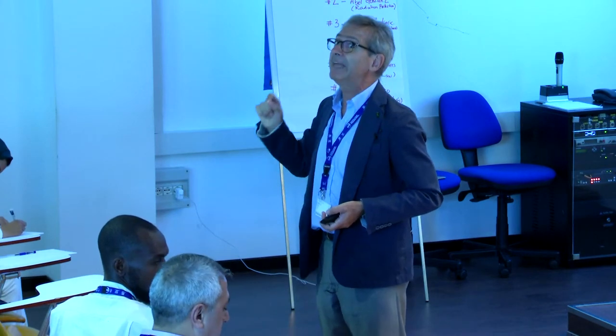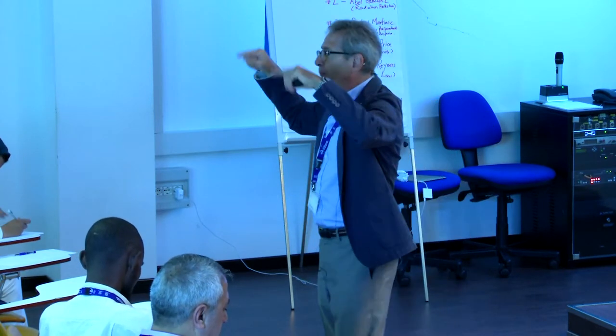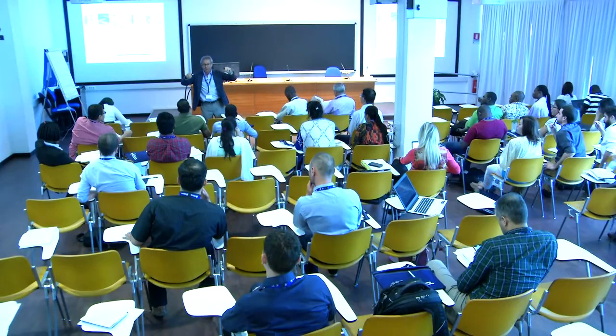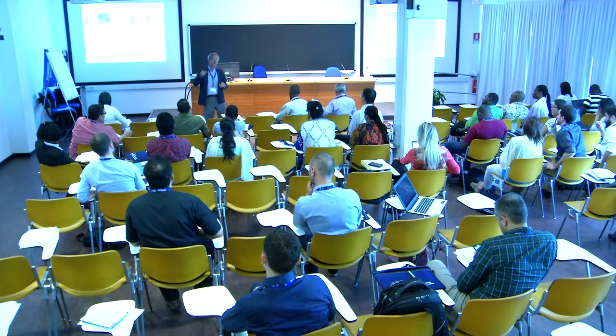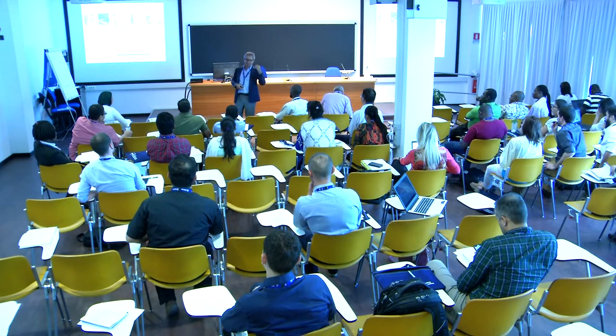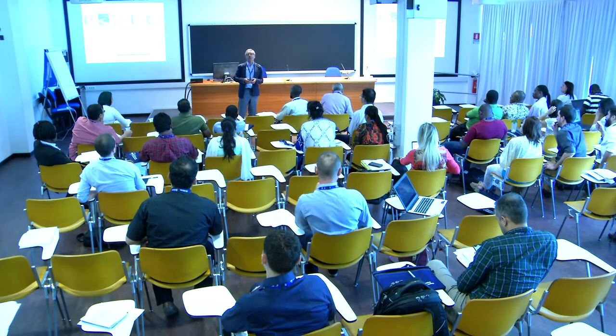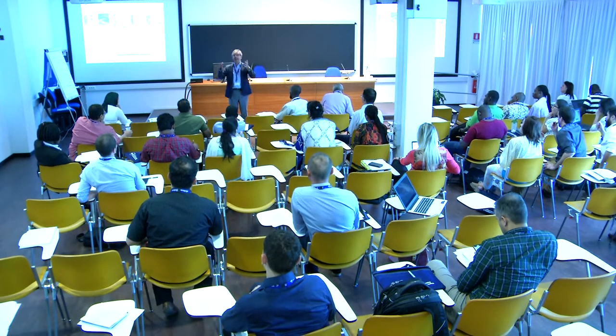Sometimes also the multi-reactors, you have in the same site the multi-reactors. And the fact is that you combine a posteriori the PSA of the single unit for a multi-unit doesn't work. Even from the mathematical viewpoint, it is not correct. So thank you for the question, because we are just launching a CRP in my section, which is the PSA for multi-unit and multi-reactor sites. There is something to be done, even from the theoretical viewpoint. And we have seen in Fukushima that a level 1 in one of the reactors can affect the level 2 in another reactor, which was not considered so far.